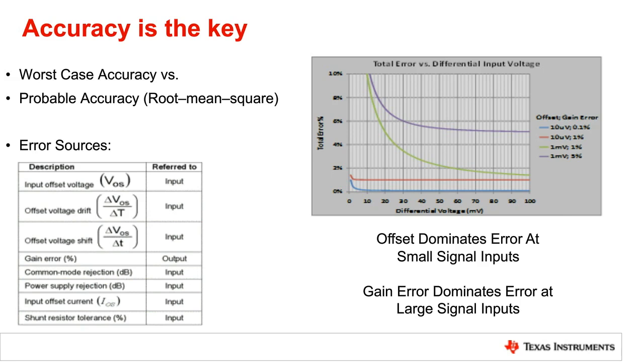And so the chart here shows a representation of the different errors and how they impact the system. So the differential voltage along the x-axis is essentially related to how much current we're sensing, so the voltage drop across the resistor. And then we can see the total error here. And as we can see, when the differential voltage is lower, a large gain or a large offset error can have a significant impact. So let's say a 1 millivolt error on a 10 millivolt signal, that's going to be a 10% error that's potentially injected inside the system. However, as our differential voltage increases, we start to see gain error become the primary contributor to total system error.